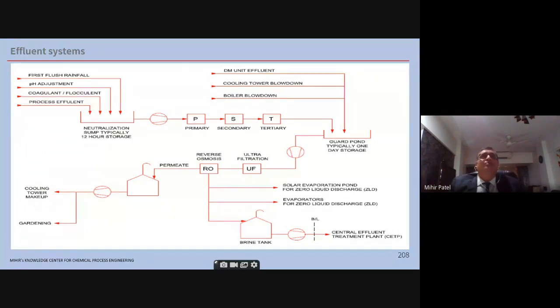Now, as you see on the top, the clean effluents, DM unit effluent, which is basically, let's say you have a resin-based DM plant, where you are using the strong acid cation, or you are using a strong base anion mixed bed unit. They have to be regenerated. So that is this effluent. It is neutralized there in a sump pit and then pumped to this guard pond. So that is clean effluent. Cooling tower blowdown is there, boiler blowdown. These are clean effluents. From here, basically, now this pump, you can decide.